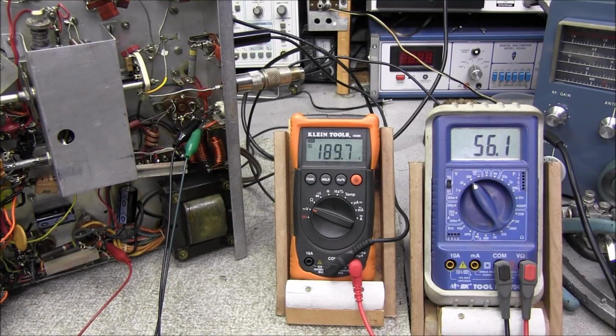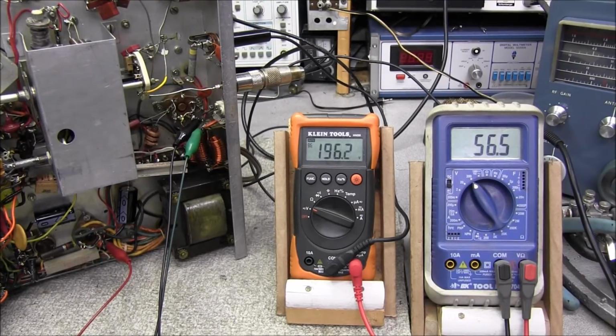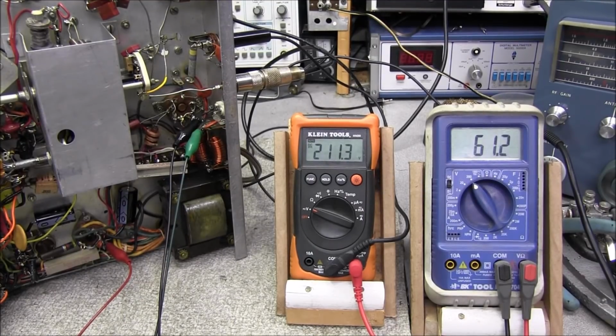See our high voltage is up over 190 volts at 56 volts input. Should reach right close to about 395 to 400 volts. 77 volts. We're at 80 volts at 275. Looking good. Dial lamps are on.